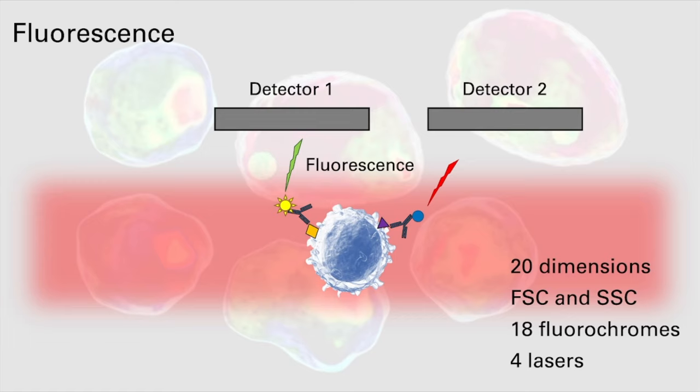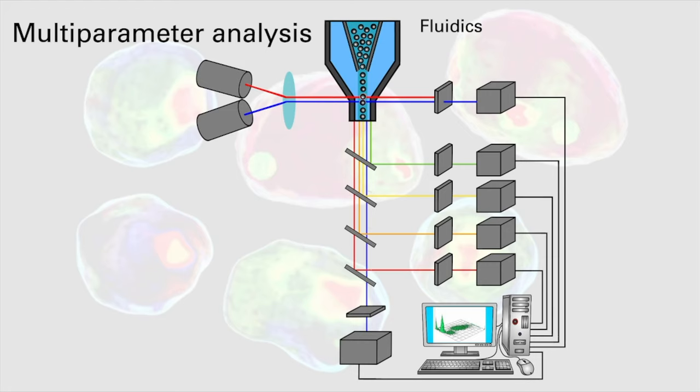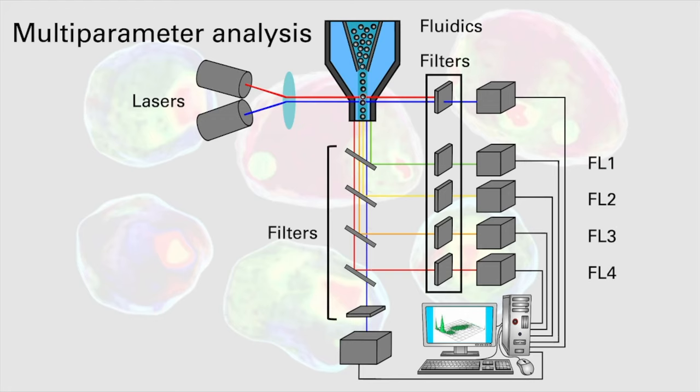Machines with five and even six lasers which can increase the number of parameters to around 50 do exist but these machines at the time of making this video are rare and incredibly expensive. In this example setup we are keeping things relatively simple with two lasers that emit light at different wavelengths with fluorescent detectors each that can detect emitted light at different wavelengths which when combined with the forward and side scatter detectors allows for up to six different parameters to be detected simultaneously.